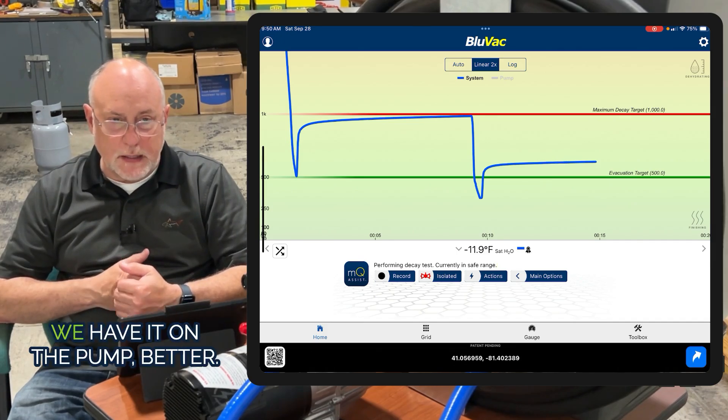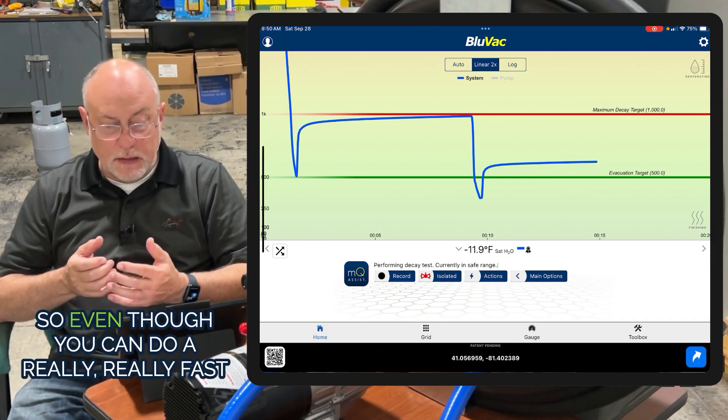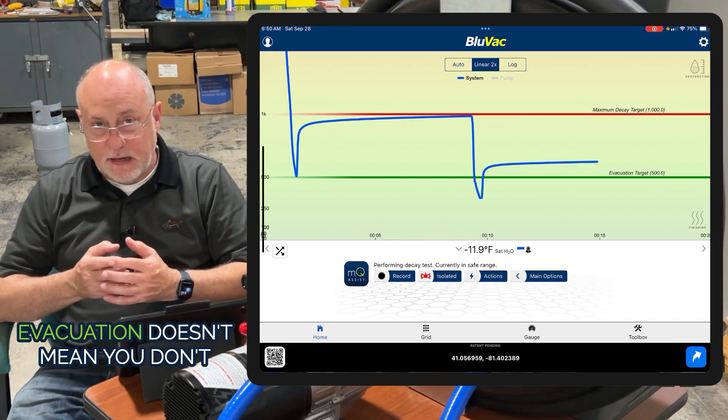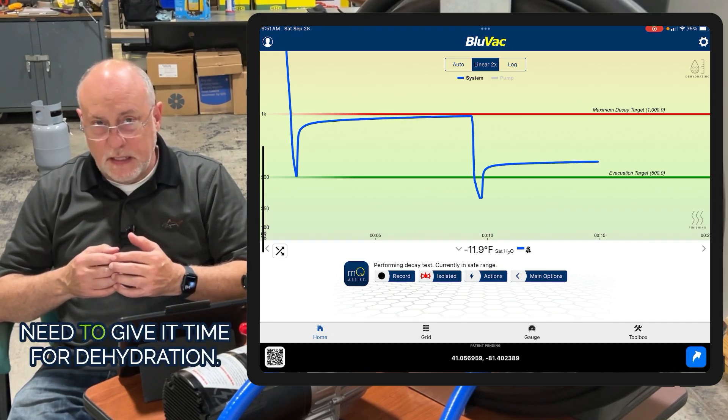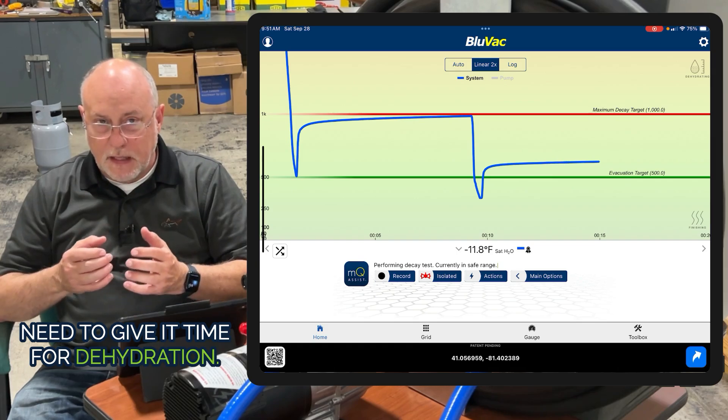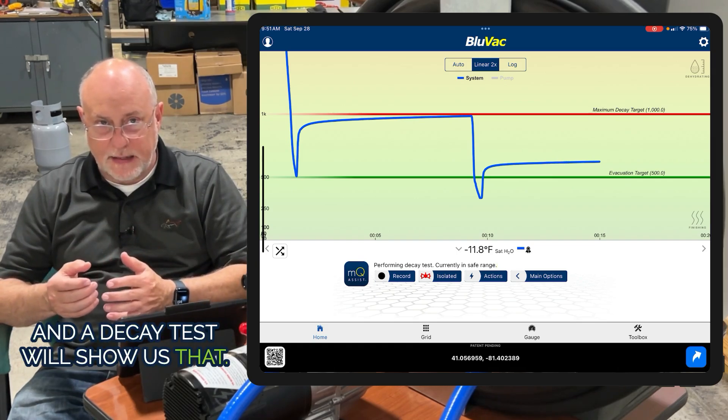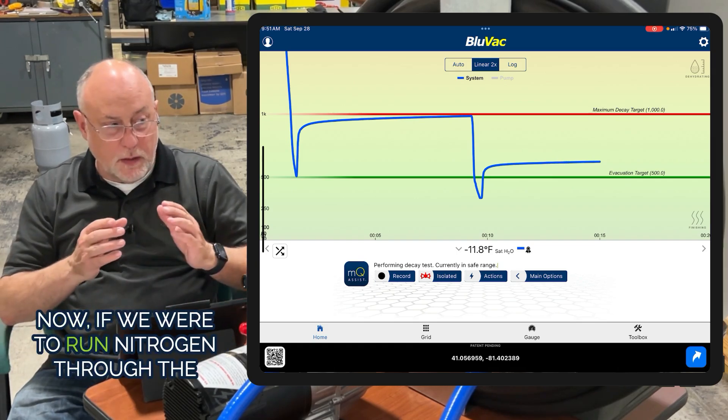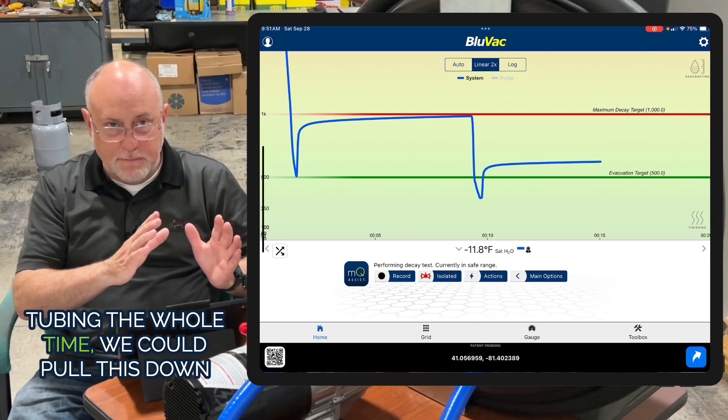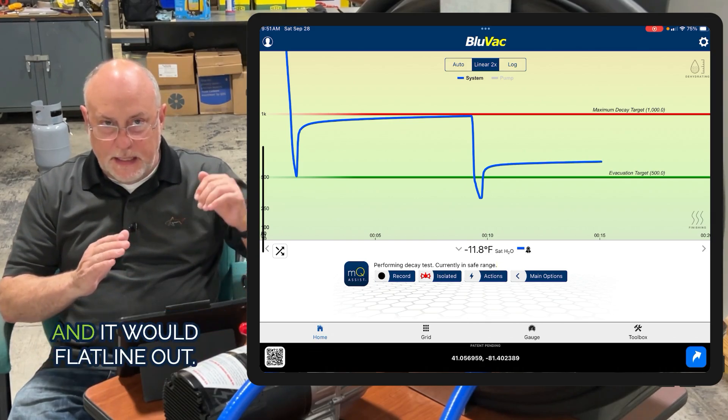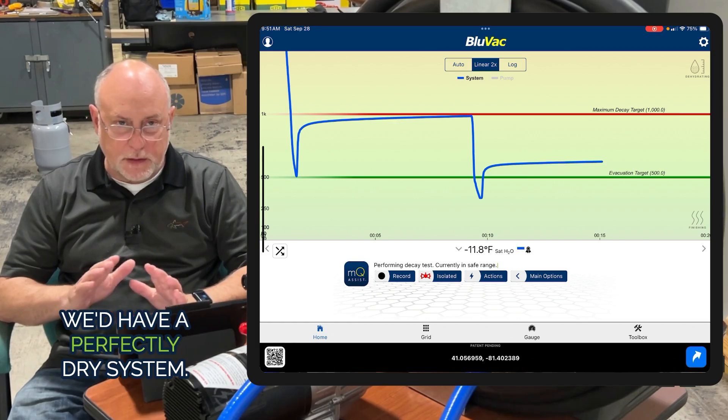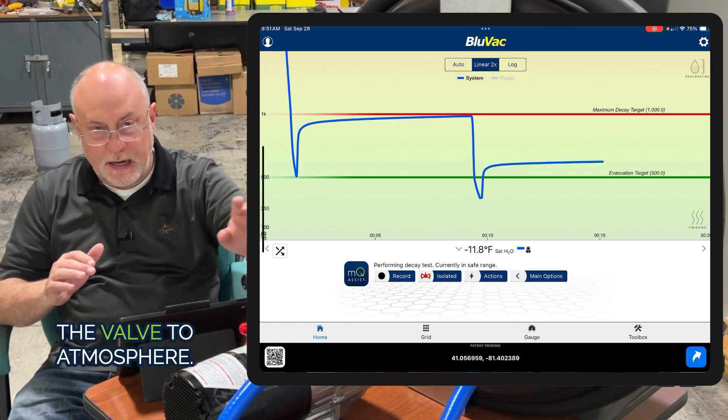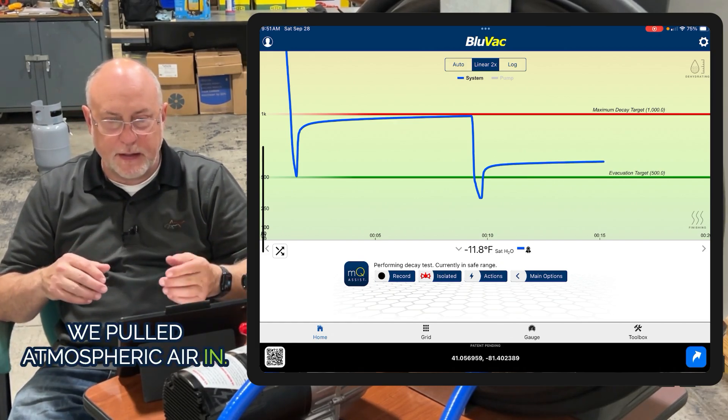The longer we have it on the pump, the better. Even though you can do a really fast evacuation, doesn't mean you don't need to give it time for dehydration. A decay test will show us that. Now if we were to run nitrogen through the tubing the whole time, we could pull this down and it would flatline - we'd have a perfectly dry system. In this case, I opened up the valve to atmosphere.